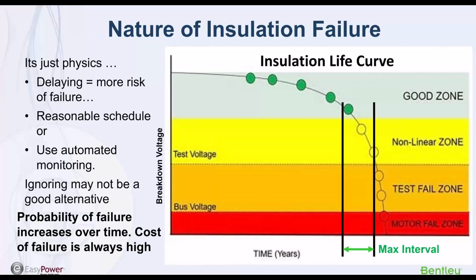Just as an example, when looking at dielectric materials, there is potential degradation over time. Your testing needs to be done so you detect the degradation, not so you go and do a test and then find out your insulation is just about failed. Because if it's just about failed, you probably waited a little too long to do that test.